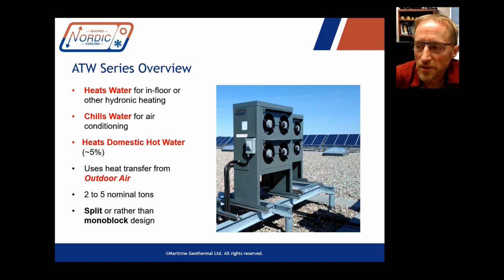Maybe. The thing with air source heat pumps is that in practice, this is unlike a geothermal heat pump, but as it gets colder outside, the COP and the capacity of the heat pump go down and your heat load goes up. So for an average house, it's expected that backup heat or auxiliary heat will be running alongside the heat pump in order to satisfy the load, and the heat pump's going to be running all day when it's reasonably cold out already. So you don't have a lot of extra capacity to keep it on and heat an enormous tank of water in order to have thermal storage. Because in practice, air source heat pumps are running all the time when it's cold out anyway, just because of their reduced capacity.